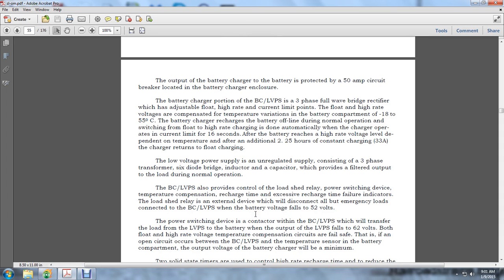enclosure. The battery charger portion of the BC LVPS is a three-phase full wave bridge rectifier, which has adjustable float and high rate voltage and current limit points, and the voltage is compensated with the temperature variation of the battery compartment of -18 to 55 degrees Celsius. The battery charger maintains the battery charge off of the line during normal operation, switching the float to high rate of charging automatically when charging operation current limit is reached, and the battery reaches high rate voltage dependent on the temperature. After an additional 2.25 hours, the constant charging current of 33A returns to the floating charge.